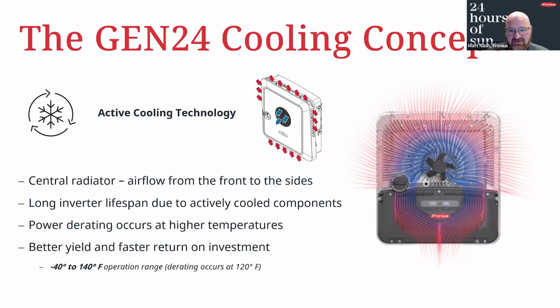Another key feature is the active cooling technology. So with the Gen24, you have a central fan that intakes from the front and then disperses heat throughout the sides of the inverter. What this does is it gives a long inverter lifespan due to actively cooled components. It does power derate at a much higher temperature than passively cooled systems. It also gives you better yield for a faster return on investment. And as you can see below, the operating range of these is -40 to 140 degrees Fahrenheit.